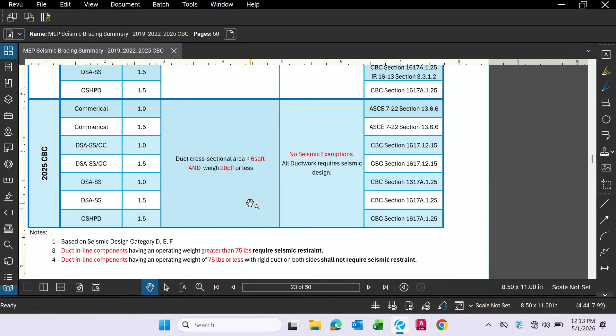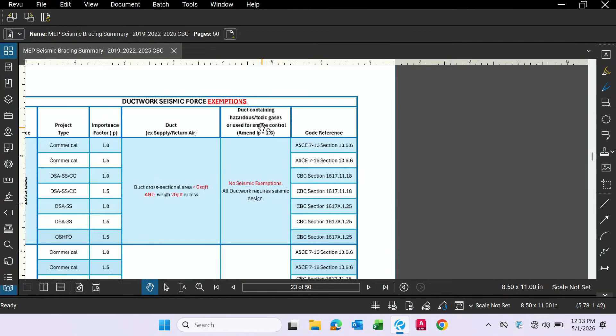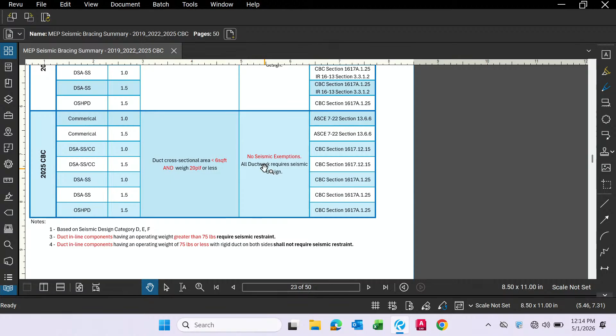Now, the only exception is if the duct contains hazardous content. So if the duct is transferring generator exhaust or dangerous chemical fumes or whatever, all of those ducts have to be braced regardless of size and weight. Pretty straightforward, right? Importance factors 1.0 and 1.5, same requirement for ductwork. So ductwork is a little more straightforward.